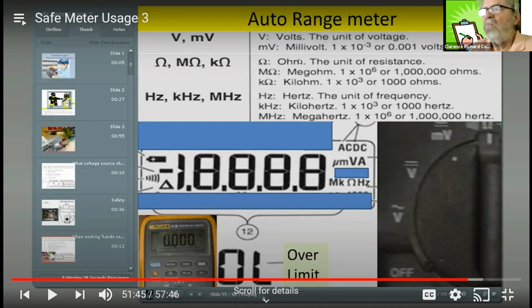When you're reporting to some of the people helping you troubleshoot, they might want to have something in millivolts DC typically, and that's where you normally get millivolts DC coming from the load cells. So you got to make sure you have it on DC, and be looking for the millivolt range. This is for ohms. This is for megaohms. That means millions of ohms. Kilohms, hertz, kilohertz, megahertz.